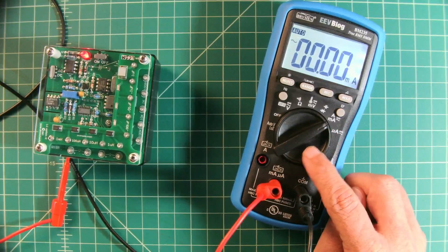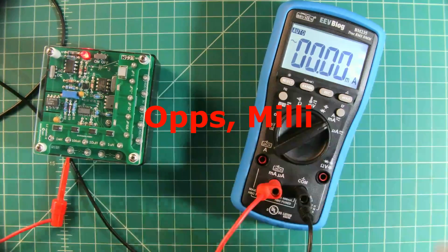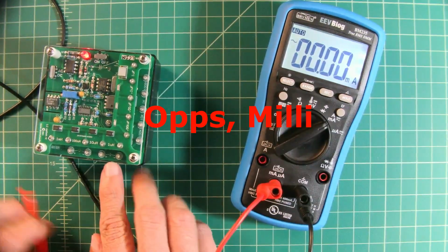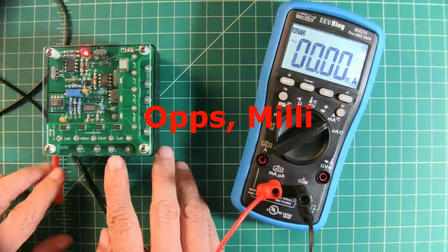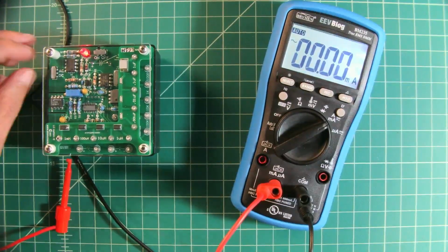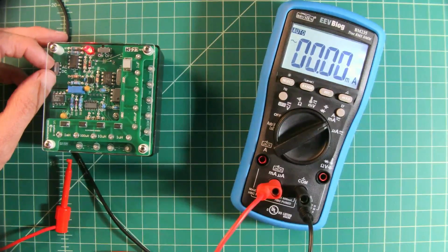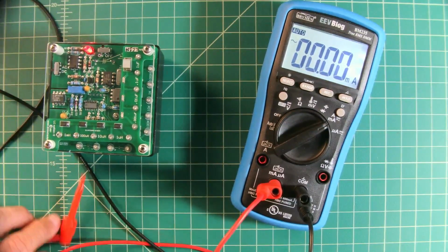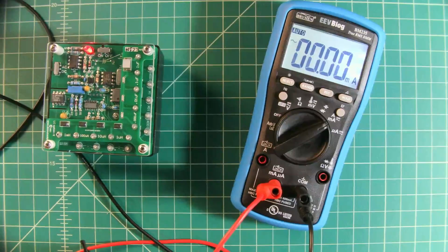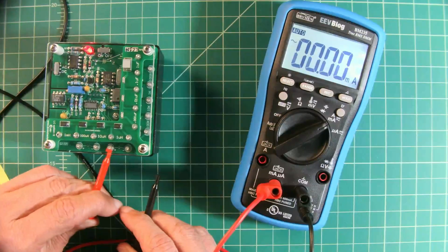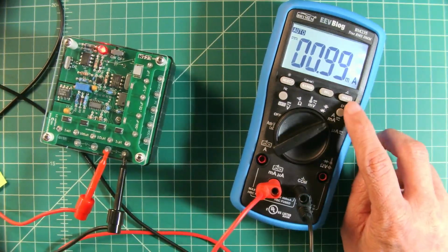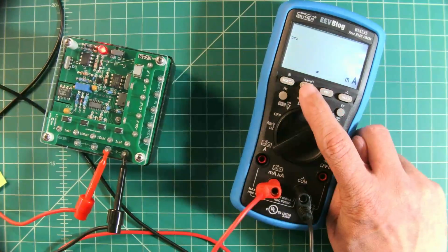Okay, what we've done is we've switched this to milliamps. And here we have the I for current. We have positive and we have negative terminals. And we are going to test our DC current source, which should be 0.9996 milliamps. And here we have 0.99.